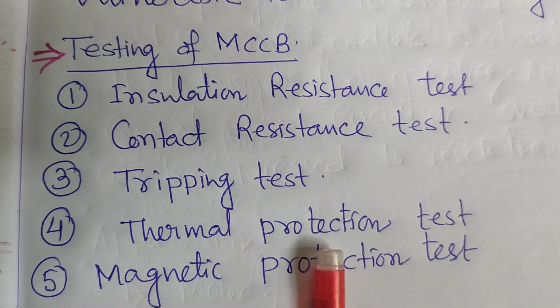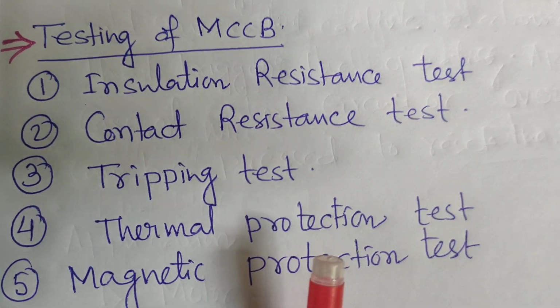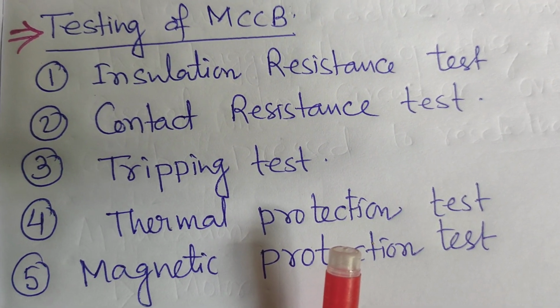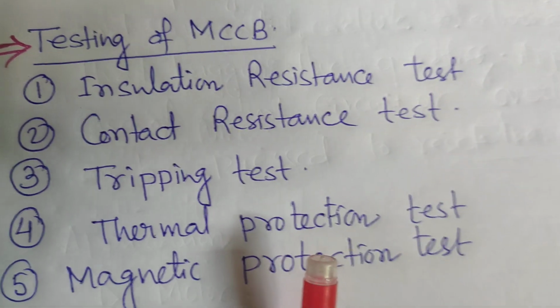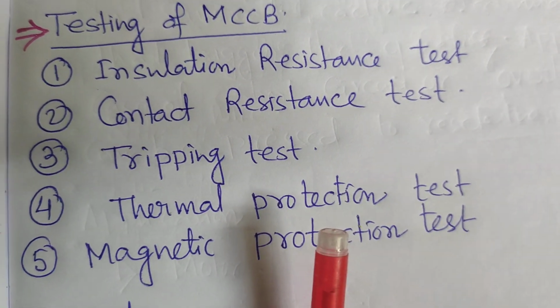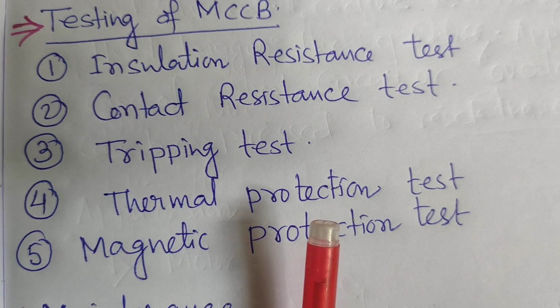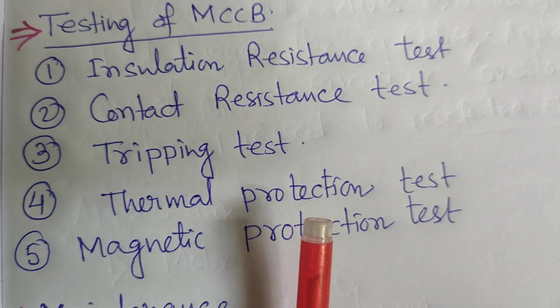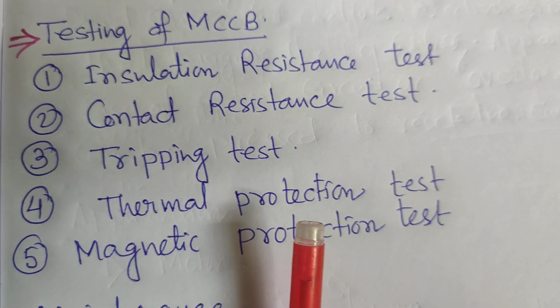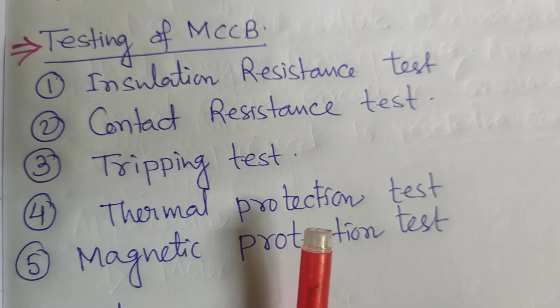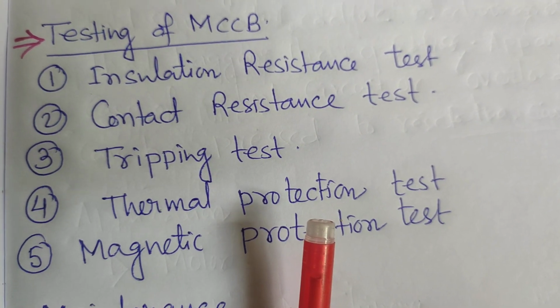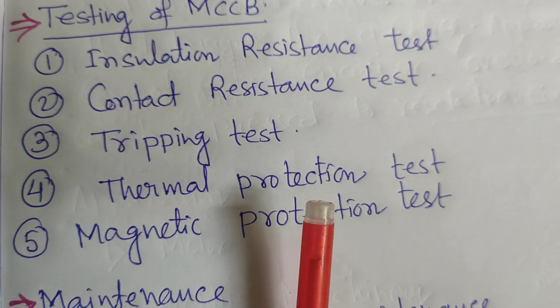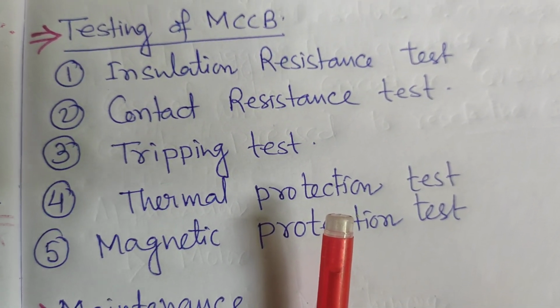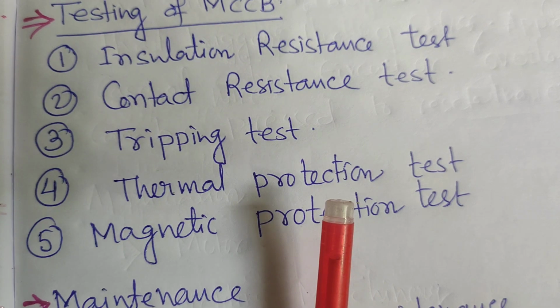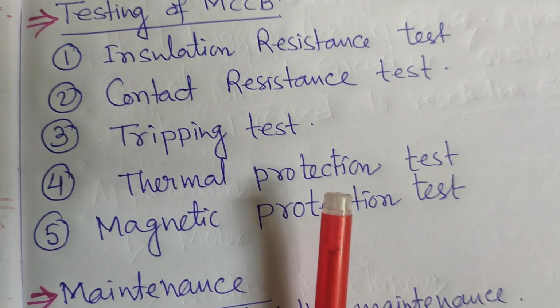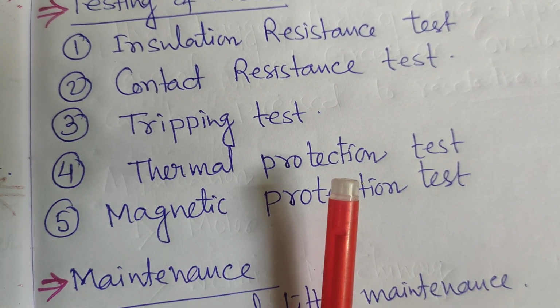Tripping test: we have to check by the tripping notch whether the circuit breaker trips properly or not. Thermal protection test. Inside the MCCB, two types of coil are there: one is the thermal coil, one is the magnetic coil. A solenoid is present. One is the thermal protection, one is the magnetic protection. This is the main basis of the MCCB.